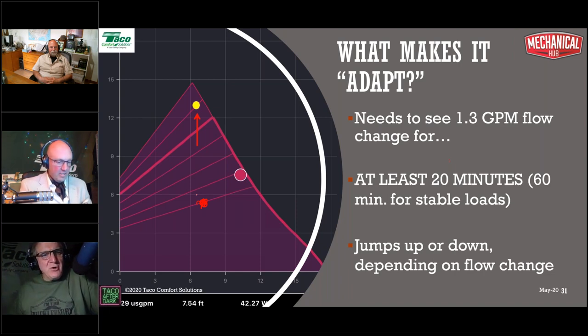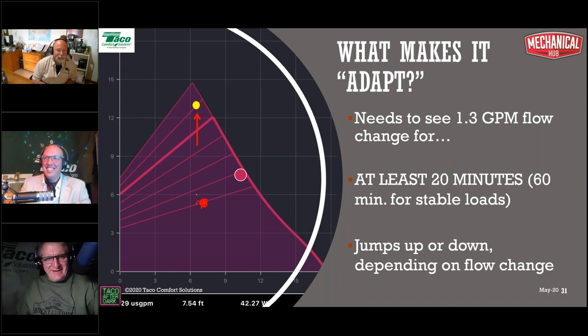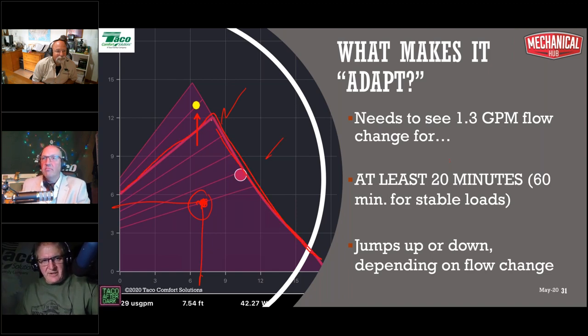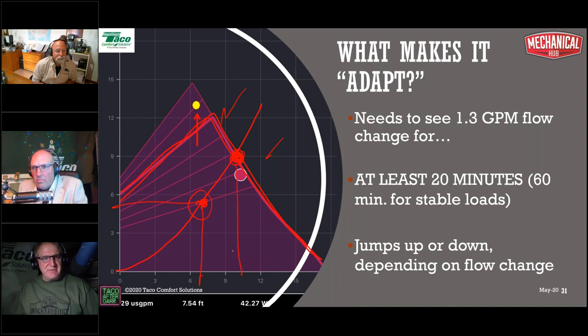Rick, where is it going to work when we first turn it on? Rick is quiet. Dave, where's it going to work when we first turn this thing on? Go ahead. I need to be here, right? But if I'm in Active Adapt and I turn this thing on, where's the system going to work? It's operating up at 6.5 at about 11 foot of head. Right there. It's going to operate on that default curve that it goes into for an hour and a half, right? So if we were to extrapolate out the system curve, I'm working right here. Full speed, maybe at about 10 gallons a minute. That's where it's working, right? It's going to work right there.